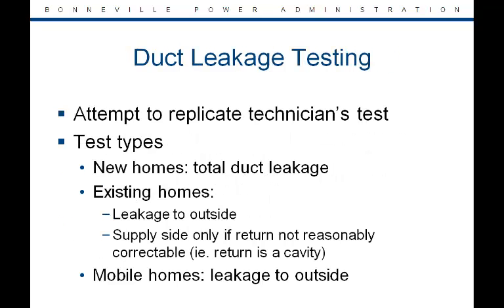Duct job inspectors will attempt to replicate the technician's duct leakage test. For new homes, this is the total duct leakage test, while existing and manufactured homes will be tested for leakage to outside. For existing homes, a supply-side test may be used if the return is not reasonably correctable, such as when the return is a cavity.